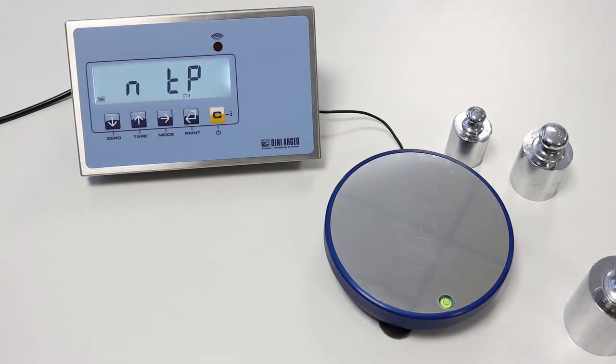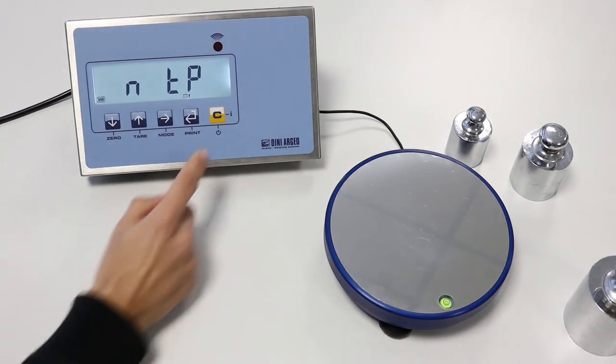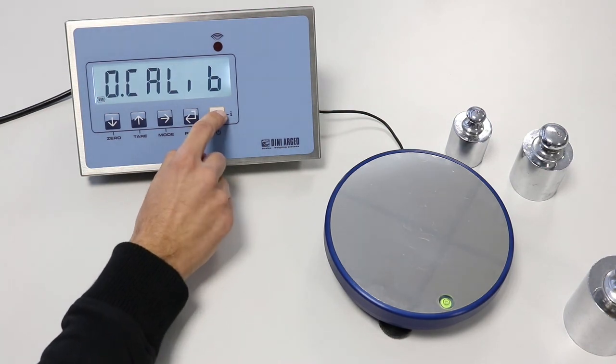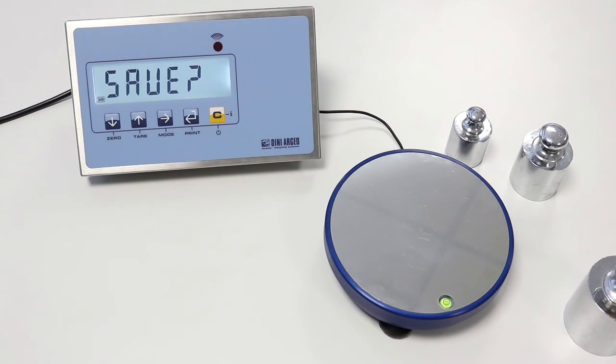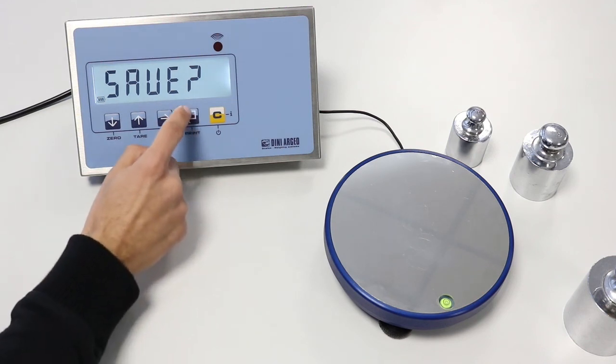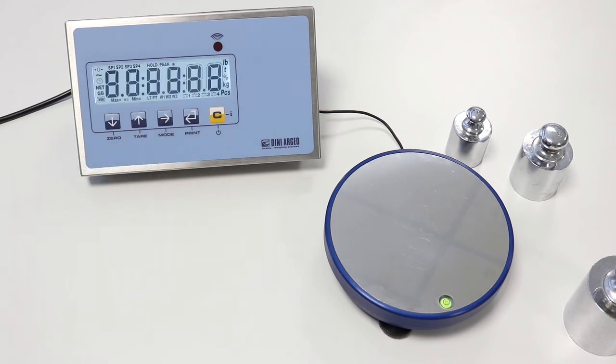To save the calibration, we press the C key many times until the save message will appear. We press PRINT to confirm and store the calibration. The indicator comes automatically into weighing mode.